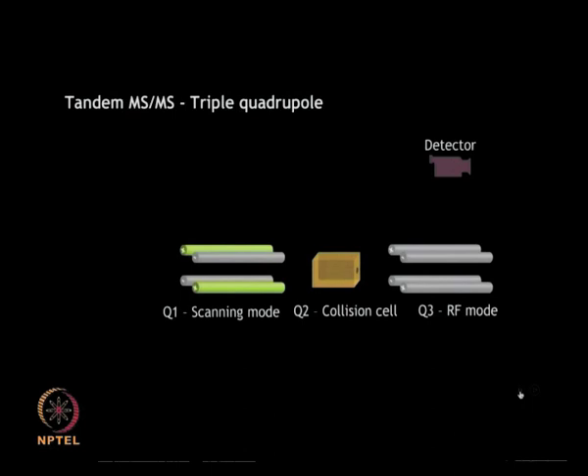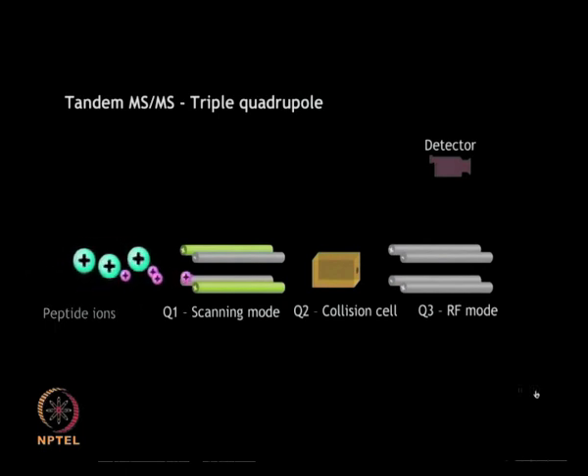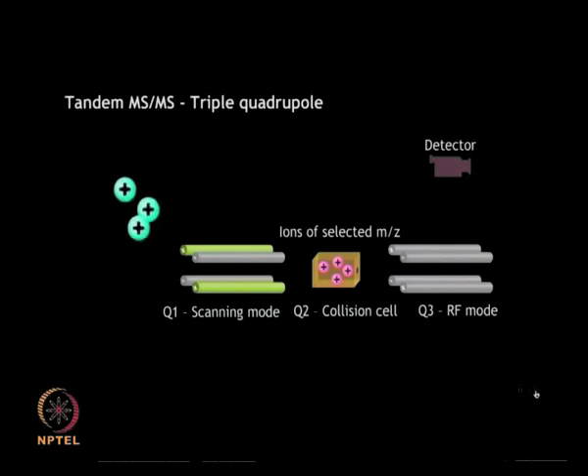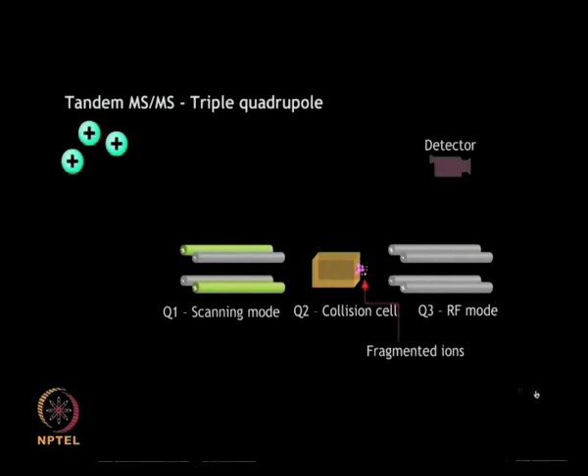The triple quadrupole consists of two sets of parallel metallic rods interspersed by a collision cell. The first quadrupole scans the ions coming from the ionization source and allows only ions of a particular m/z ratio to pass through. Once the ions are selected, they enter the collision cell where they are fragmented by collision against an inert gas like argon. The smaller fragments then enter the third quadrupole, which scans all ions in radio frequency mode to generate a spectrum based on the varying behavior of ions in an oscillating electrical field.